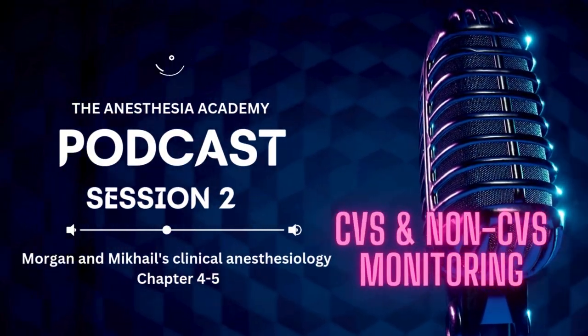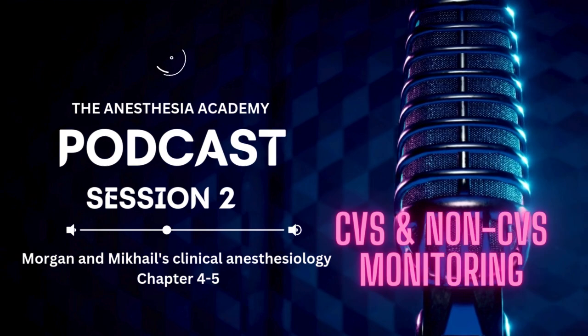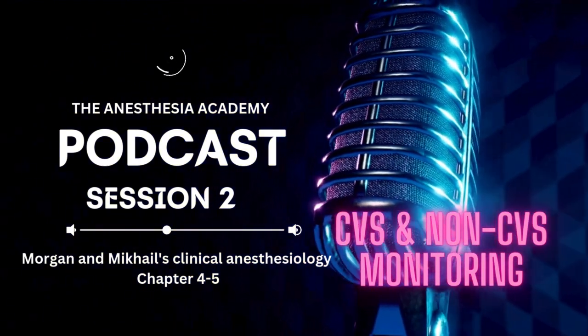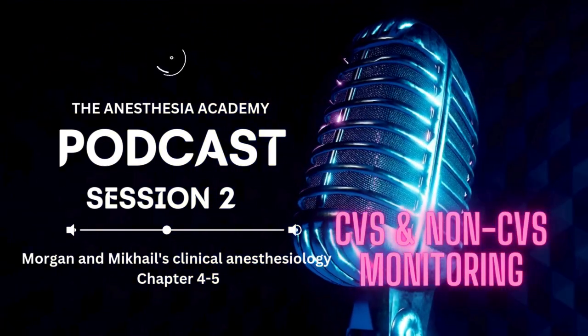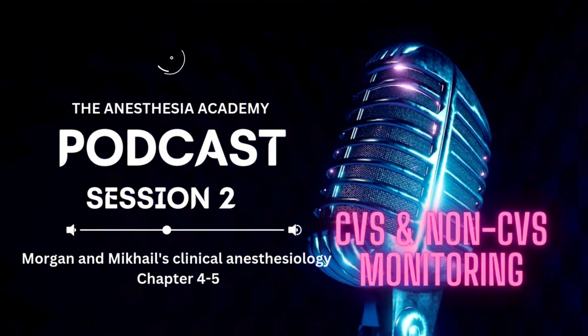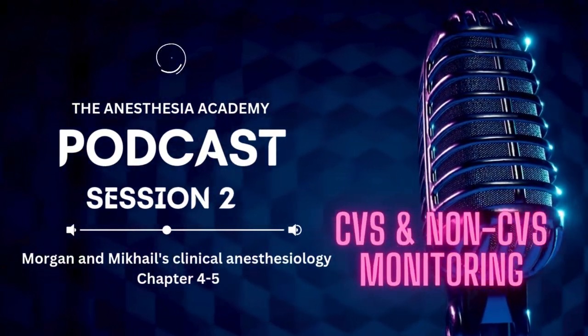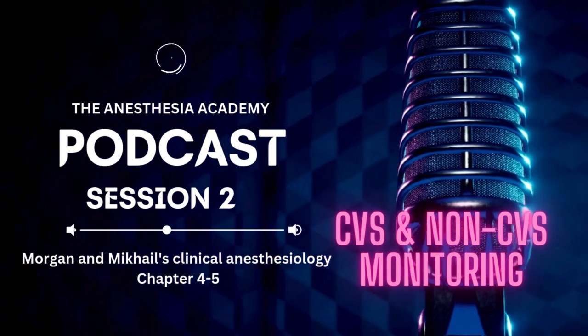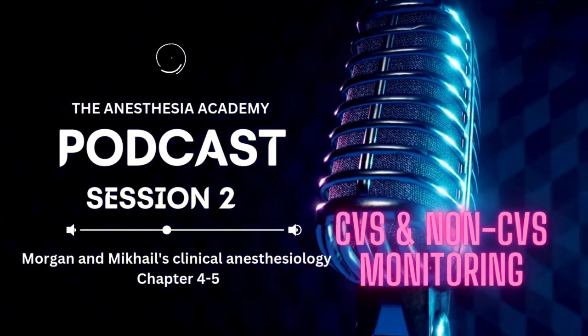What other essential safety features should we talk about? Well, the emergency oxygen flush valve is crucial. It delivers a high flow of pure oxygen directly to the breathing circuit, a lifeline in emergencies. Got it. And then there's Baralyme. It's our CO2 scrubber, removes CO2 from the exhaled breath, keeps the breathing circuit fresh.